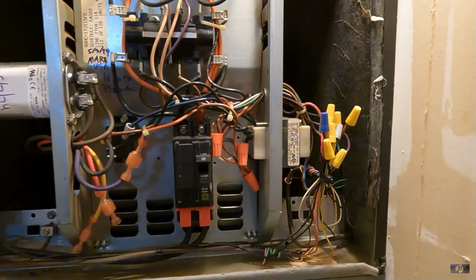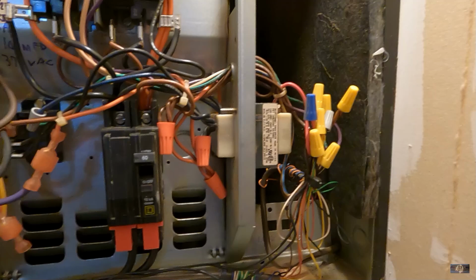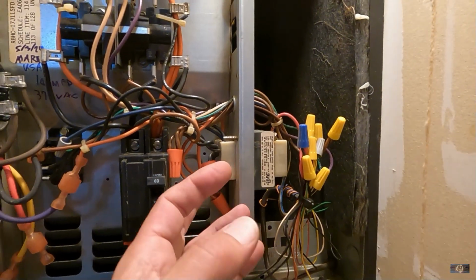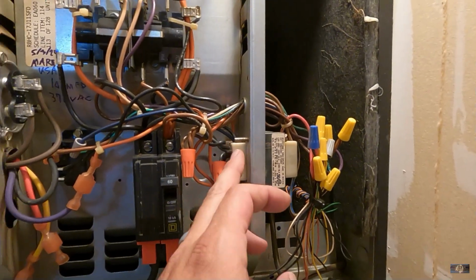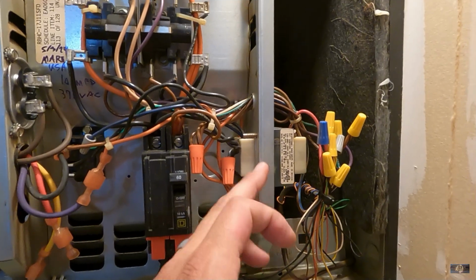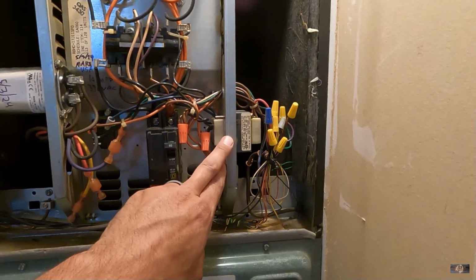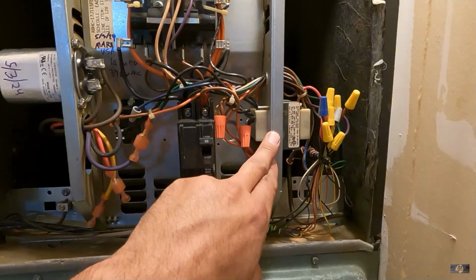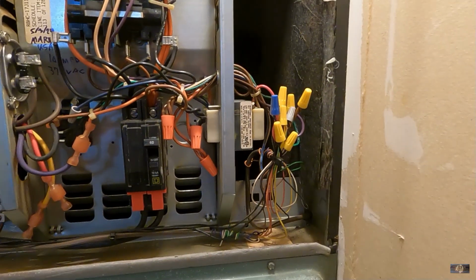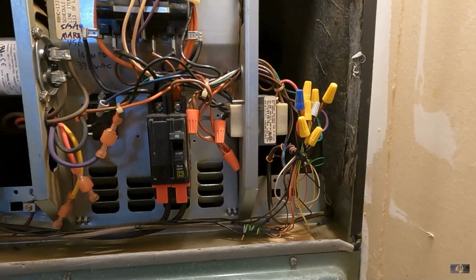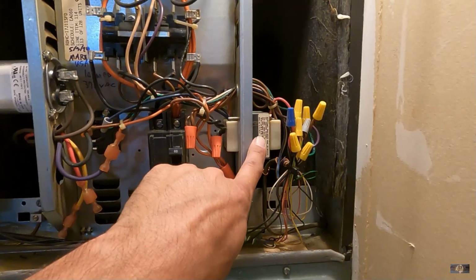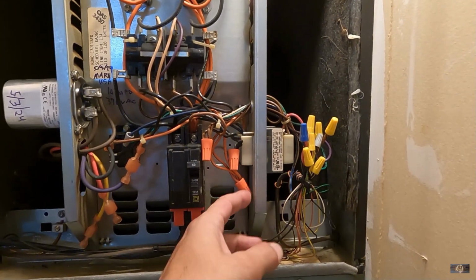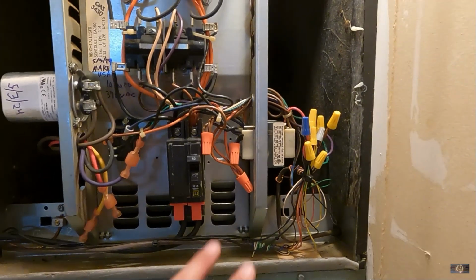So we're trying to push as much air as we can through ductwork that's too tight. The one thing I will bring up again, and I've mentioned this several times, these Rheem Ruud units don't have an inline fuse in the transformer on the low voltage side. So actually on one of the downstairs units here, we had a shorted contactor coil, and it took out the transformer. So when I replaced the transformer, I put in a low voltage fuse on the hot side, low voltage hot side.